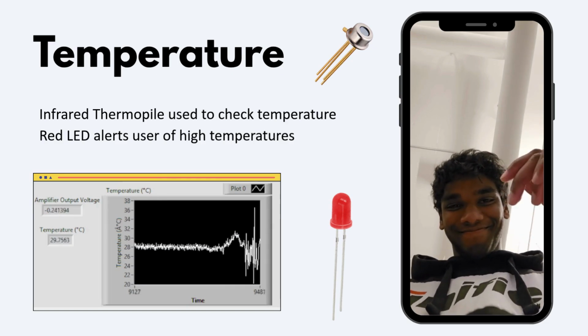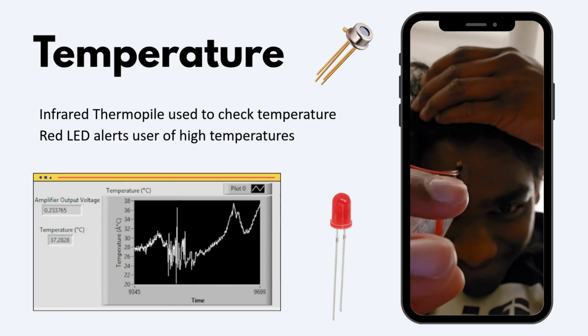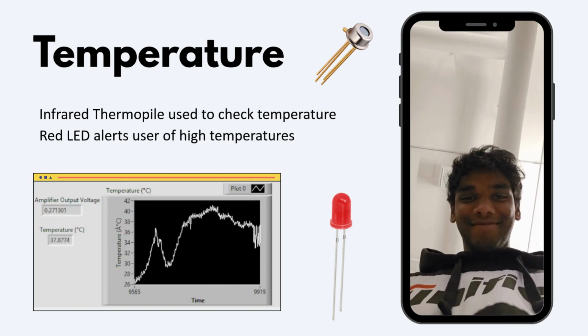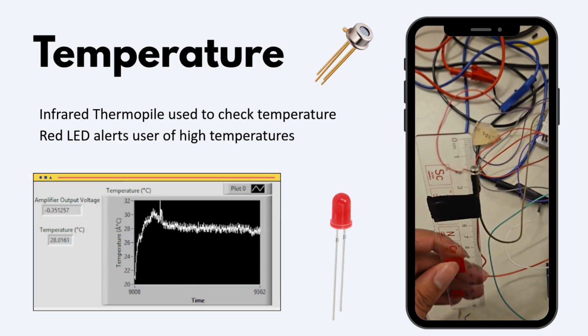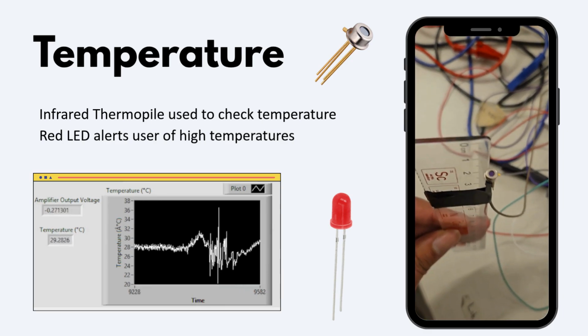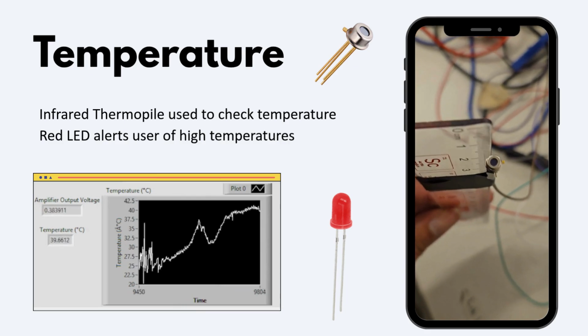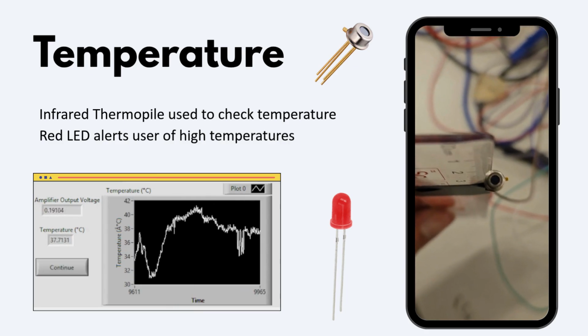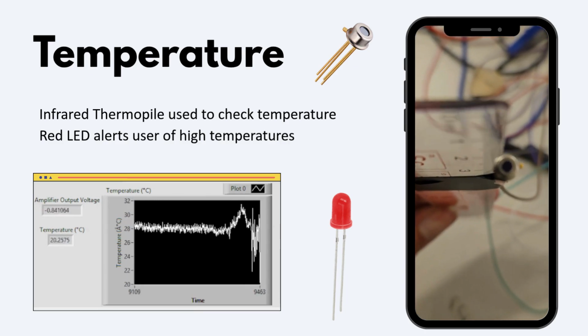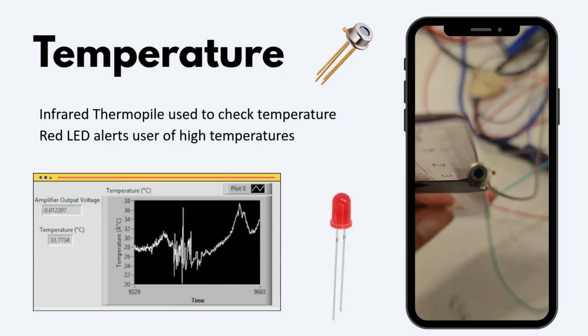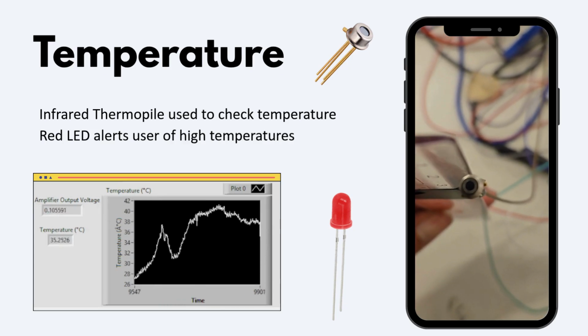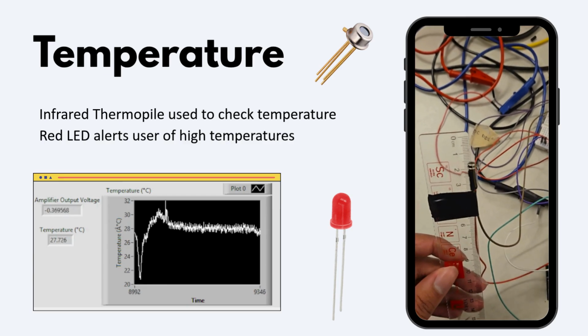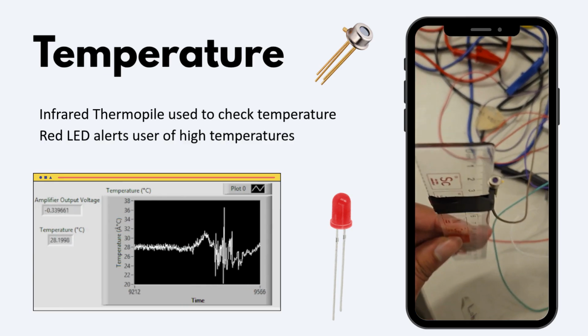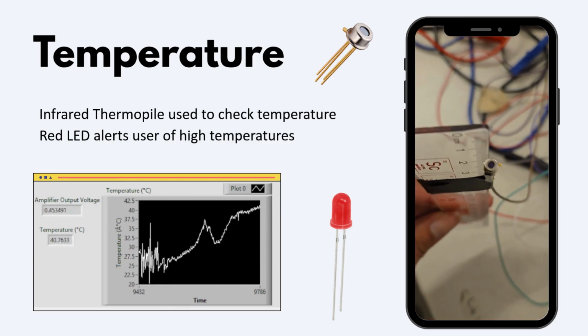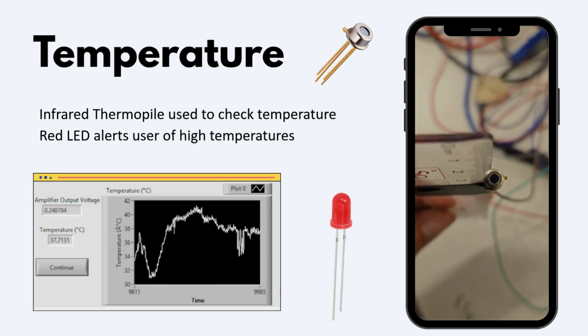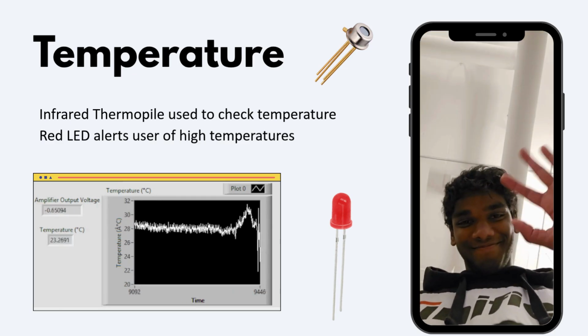The following step is a non-contact temperature check using an infrared thermopile. This sensor operates on the Seebeck effect, generating a microvolt level potential proportional to the infrared radiation emitted by the user's skin. This is a very small level of radiation, so to translate this nearly imperceptible signal into a range compatible with our Quanser DAC, we developed a non-inverting amplifier to provide a gain of 1000. This amplification allows the LabVIEW program to detect even fractional degree shifts with high resolution.